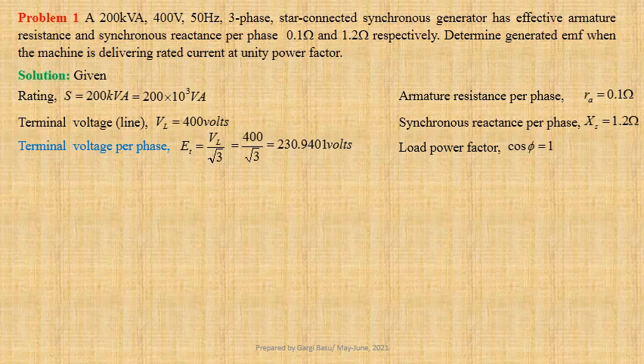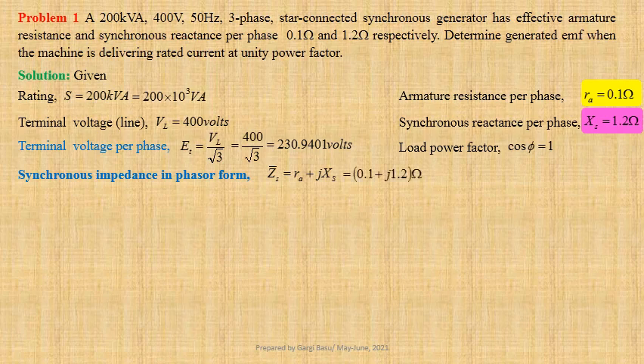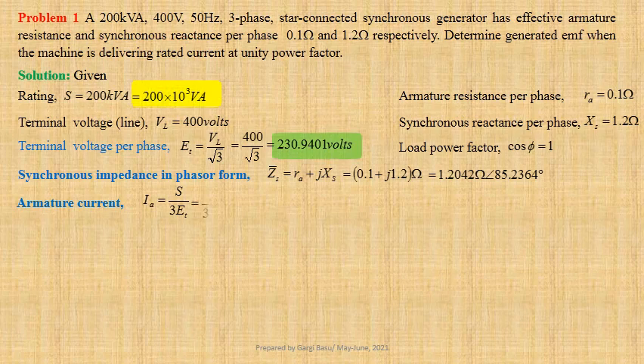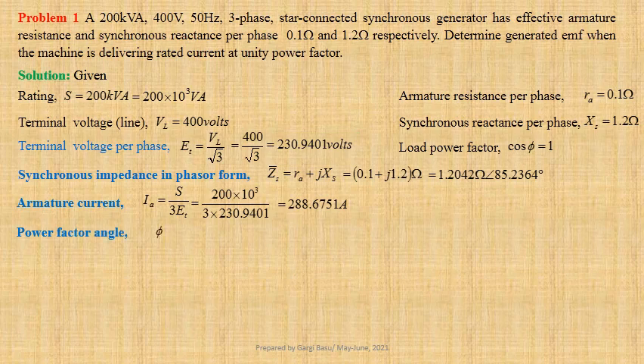Let us now write down the synchronous impedance in phasor form. ZS equals RA plus JXS, that is equal to 0.1 plus J 1.2 ohm. This may be written in polar form as 1.2042 ohm at an angle 85.2364 degree. Let us now calculate armature current. IA equals S divided by 3 times ET. Using values we get 200 into 10 to the power 3 divided by 3 into 230.9401. That gives us 288.6751 ampere. Power factor angle phi equals cos inverse 1, that is equal to 0 degree.